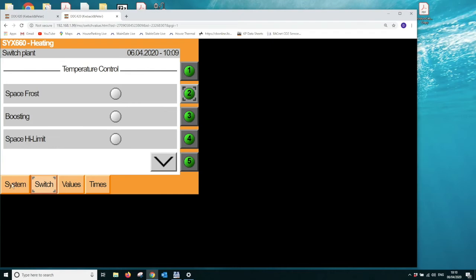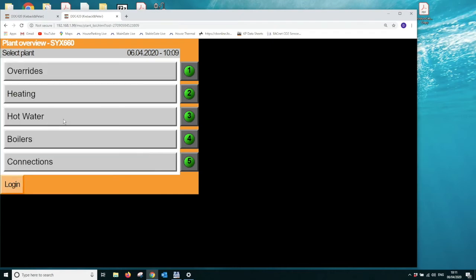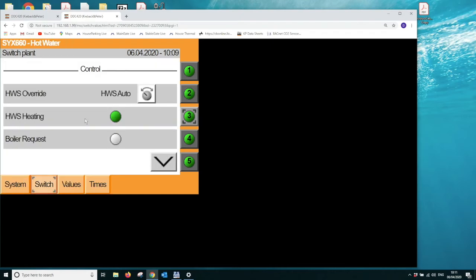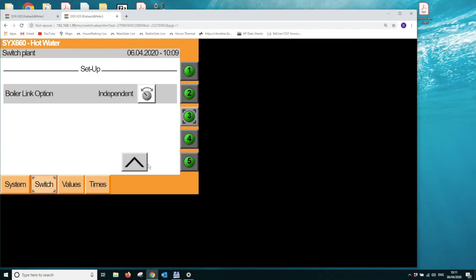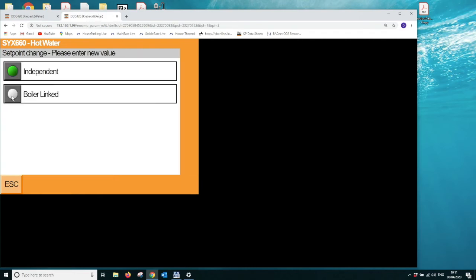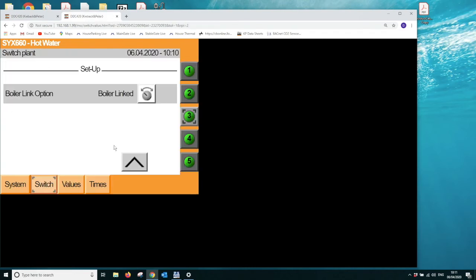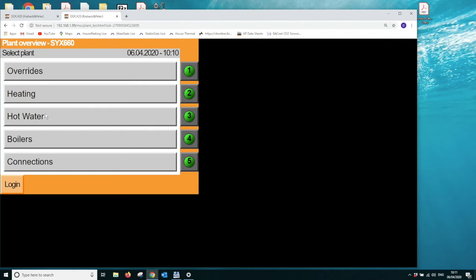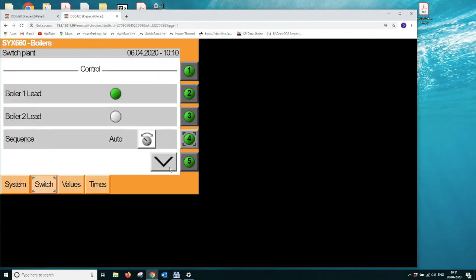We can now go back on system and choose the next option, which is hot water. Again, we tab down to the setup menu, and this is where we can choose whether the heating for the hot water is from an independent source, such as a gas-fired water heater, or we need it boiler linked. We do need boiler linked on this application, so we're going to select boiler linked, and that concludes that menu. Quite straightforward.